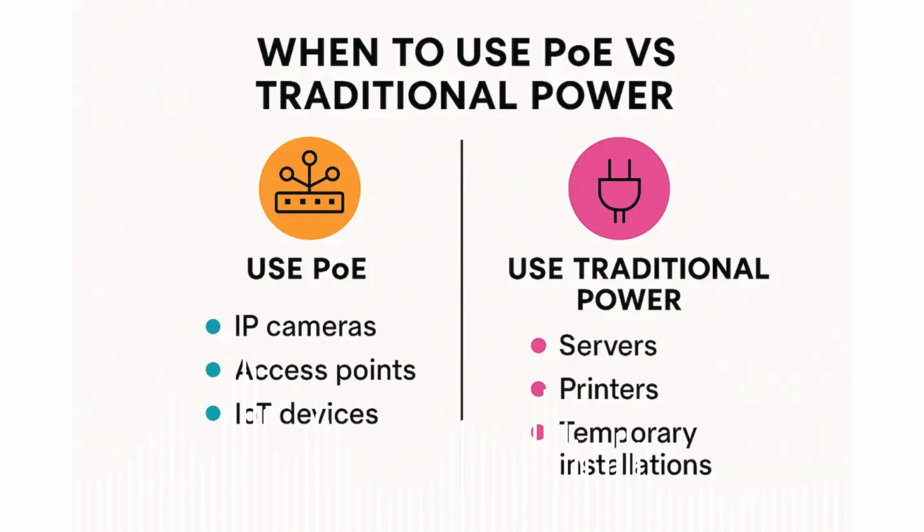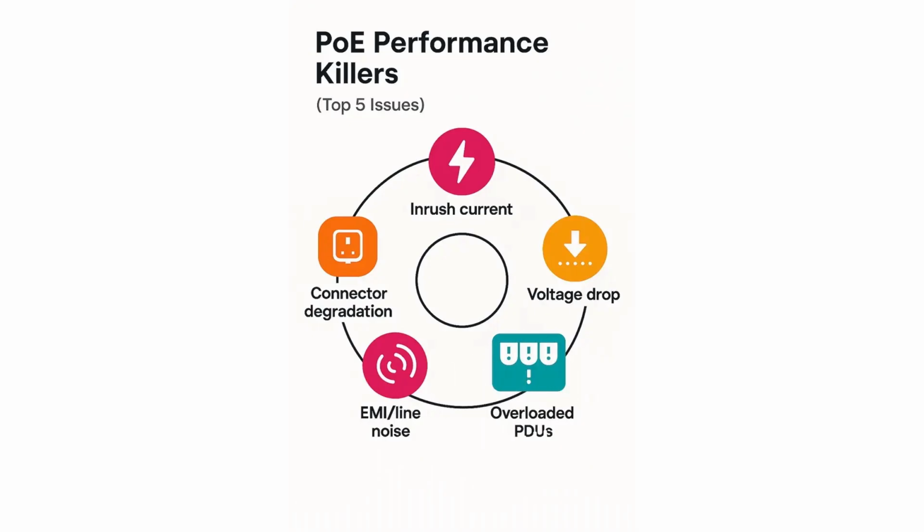Yeah, so the typical limitations around PoE: power over Ethernet is considered Class 2, which means it's low voltage. To qualify as low voltage, it has to be below 60 volts DC, and it has to be below 100 watts of power. They call it PoE++ now, because traditional PoE is only 15 watts. Then it went to 30 and it went to 60. Now it's at 90, which is really going to be the cap, because now we're hitting that 100 watt limitation. So anything over 100 watts is out of the realm of power over Ethernet.